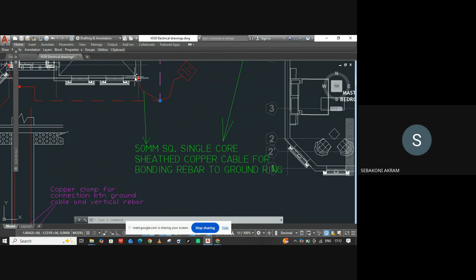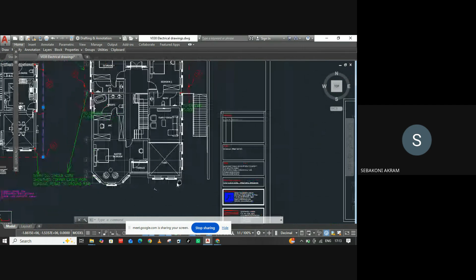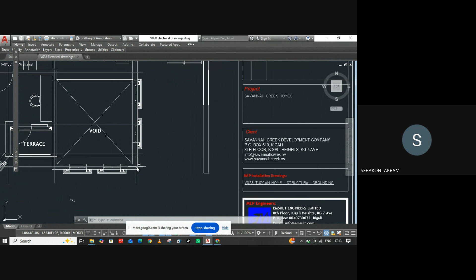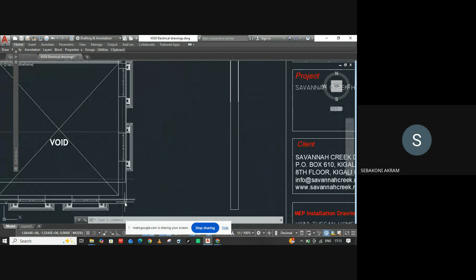Single core, then we have a connection to the rebar. So we really make sure we connect this copper cable the longest, in other words, that will run from one floor to the rest of the floors, from the ground. We're together, because if we have a column here, it really has to run up to this upper floor, because here there is no bonding. This is inside, this is in air. So up to this point it is in space. So we are trying to create equipotential up to this level of the ground.